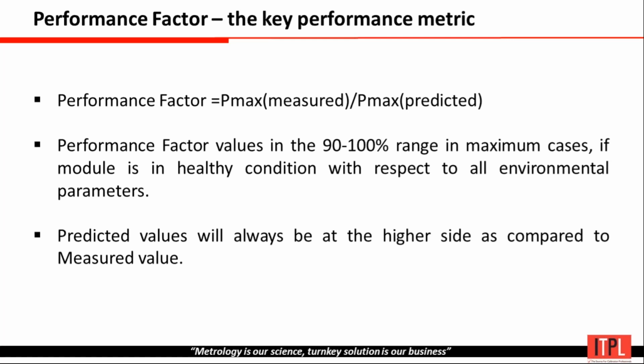The formula for the performance factor is P max measured divided by P max predicted. This value should be in the range of 90% to 100%. If the conditions are healthy with respect to all environmental parameters, it should always be in the range of 95 to 96. Predicted values will always be on the higher side compared to measured ones, because predicted tells us how much maximum power we can get at the same radiation and temperature level.